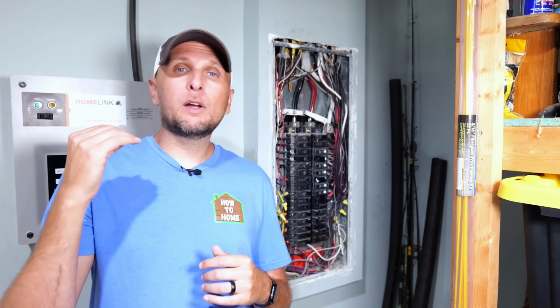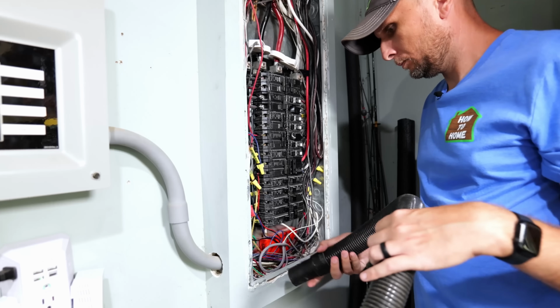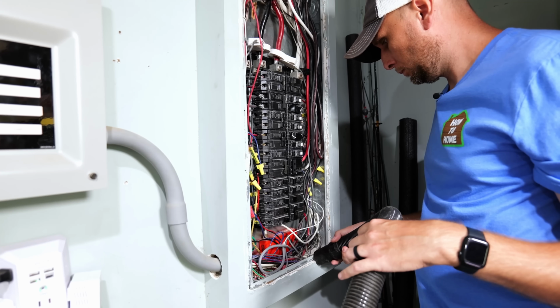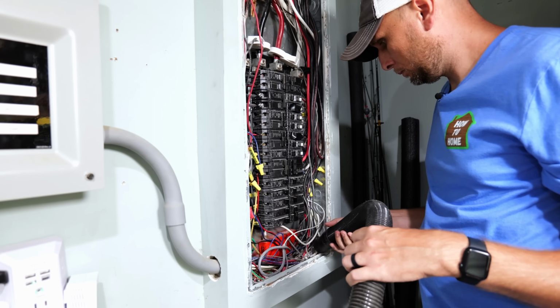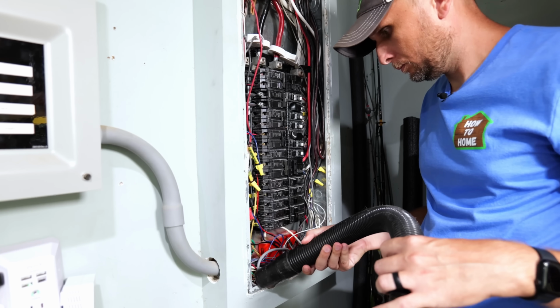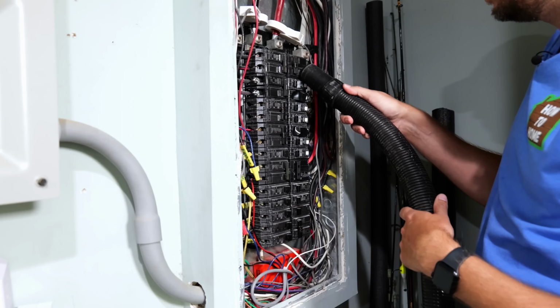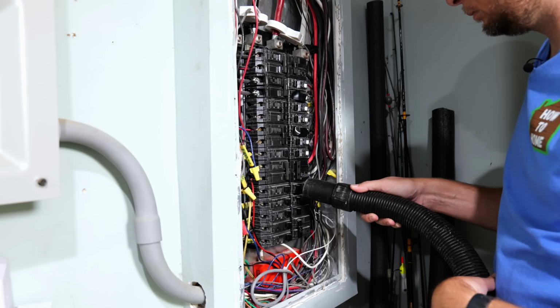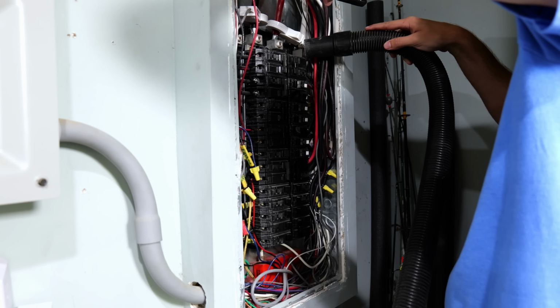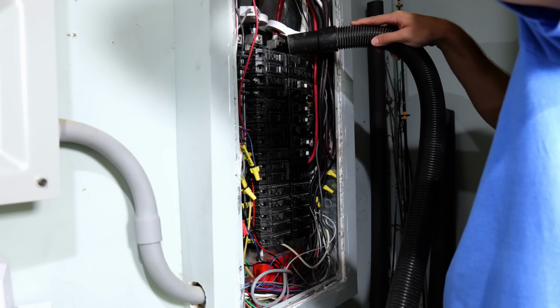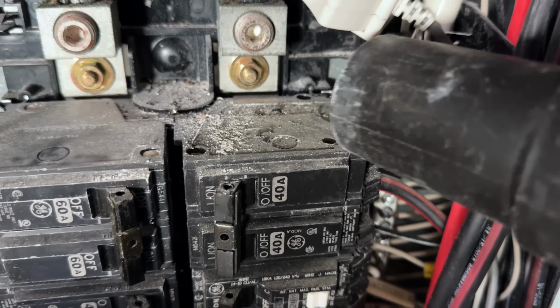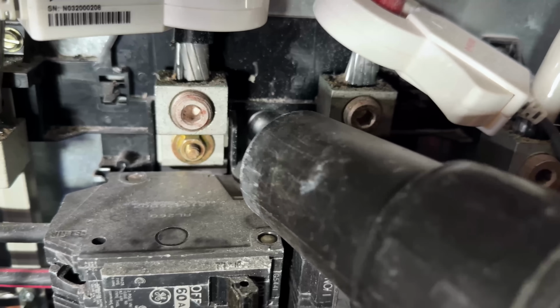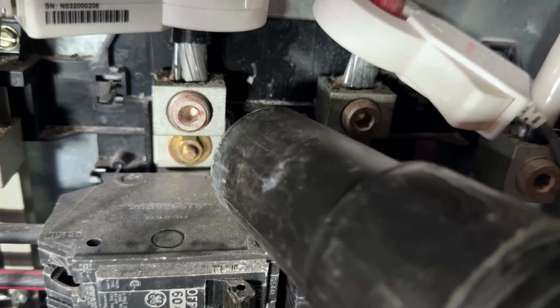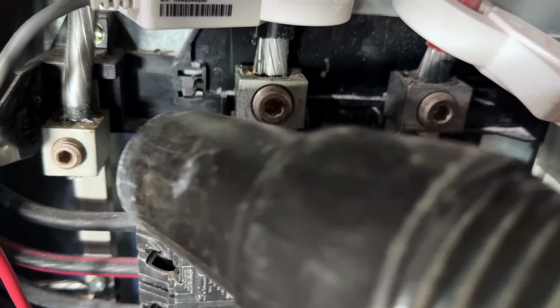Since we'll be working inside the breaker panel, make sure the power is off first. Then I like to use a shop vac to very carefully clean out the panel, being careful not to touch or get close to any possible live wires still inside even with the breaker off. Once I'm done vacuuming, I check for any gaps where debris might be getting in and make sure to seal them. If you've got open knockouts or a place where a circuit breaker used to be that's completely open, those are the major spots you want to seal up.